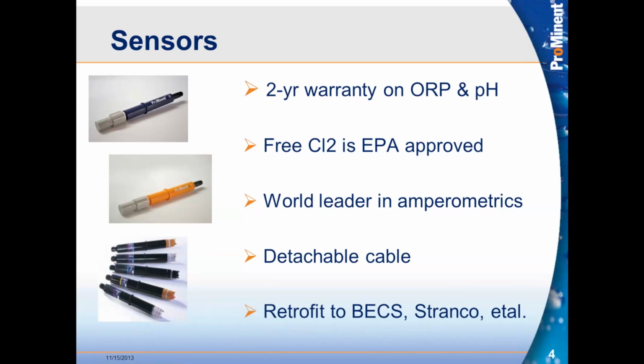And we can sense a whole host of other water-related chemicals. So we can sense oxygen levels, ozone levels, chlorine dioxide levels, free chlorine, total chlorine, you name it. If you put it into the water, bromine, anything, we can measure that to an accurate part per million and then utilize that to control the content of the chlorine.